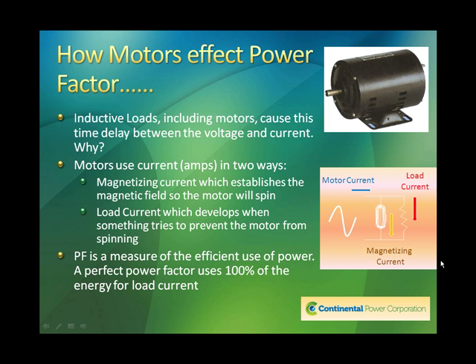And the more work that the motor has to do, the more load that is on the shaft, the more load current that flows. The magnetizing current always stays constant. No matter what the load is, you're always going to have the same amount. So very seldom, if we have a constant load that's running 24/7 in a facility, your kVAR amount will always remain constant. The kW, though, can fluctuate, and that's fairly common. Power factor is therefore a measure of the efficient use of power. Perfect power factor uses 100% of the energy for load current, none of it for magnetizing current. And that's something we can do. Now, I said that we have to have magnetizing current. You can't get away from it. The key is that we have a way that we can take the current that's flowing, store it, and supply it to the motor when it needs it. And that's where power factor correction comes in.